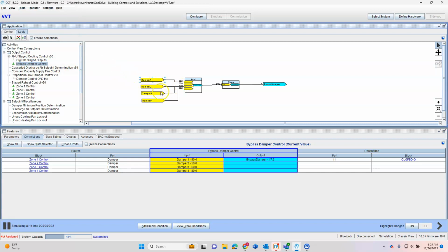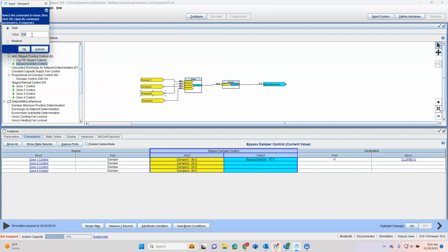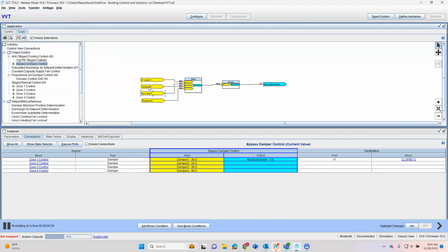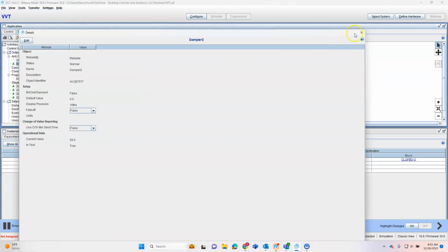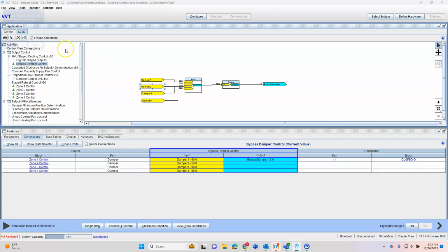And it can be in any kind of combination we want, because all we care about is airflow going over the coils. There we go. Now we have enough airflow. Our bypass damper is 100% closed, and it works. And we're connected everywhere. So that's all we needed.